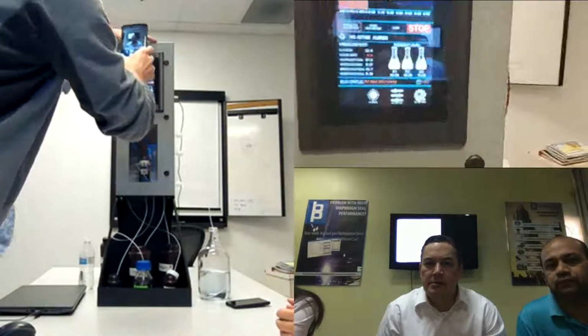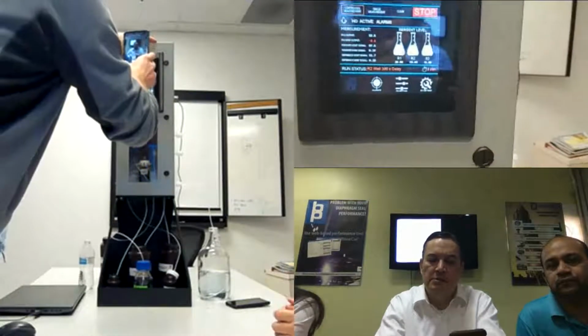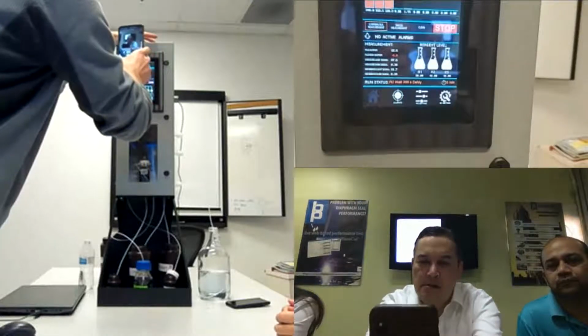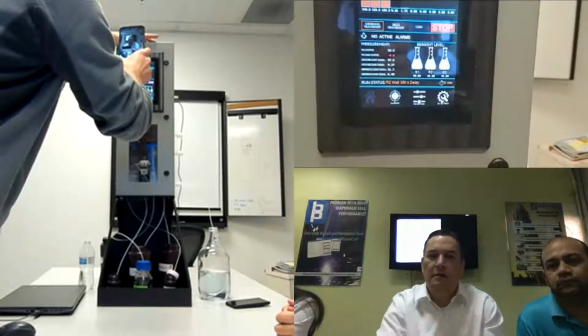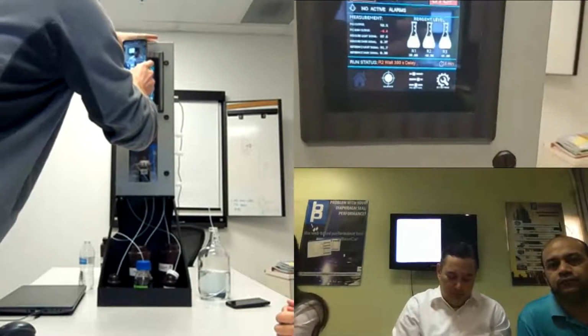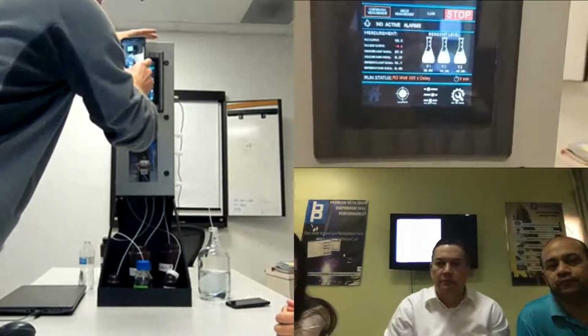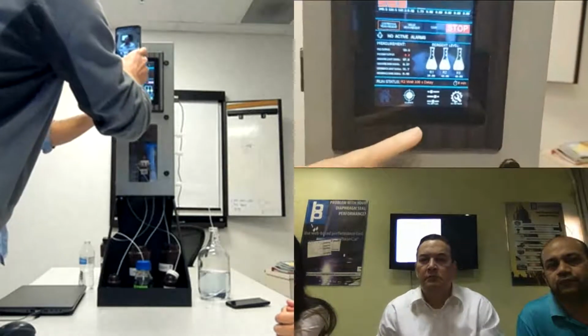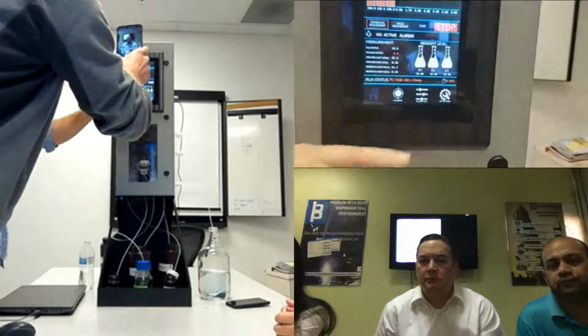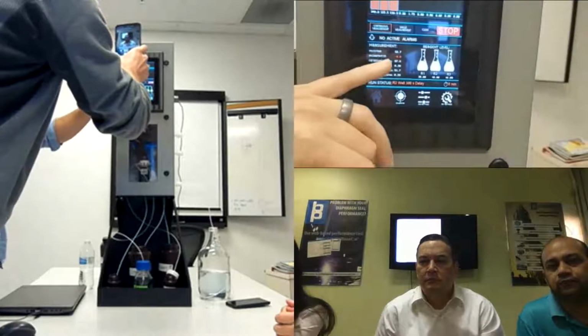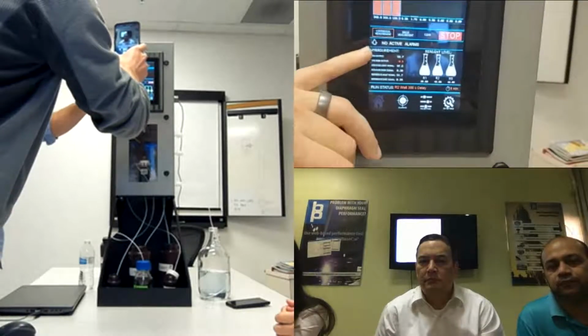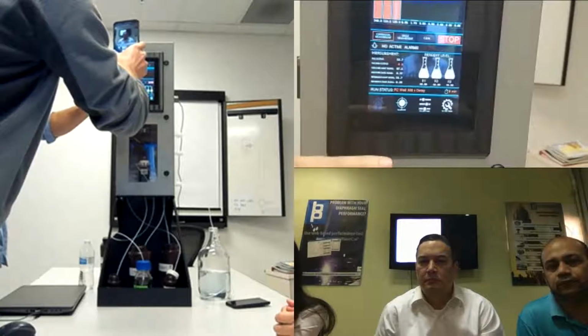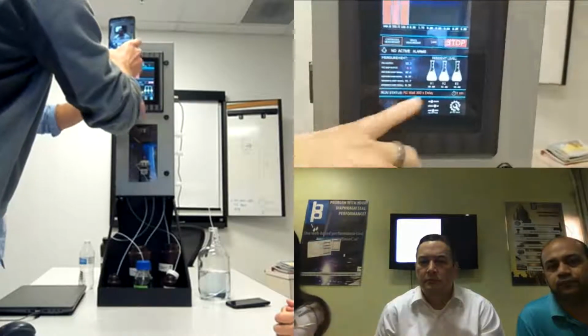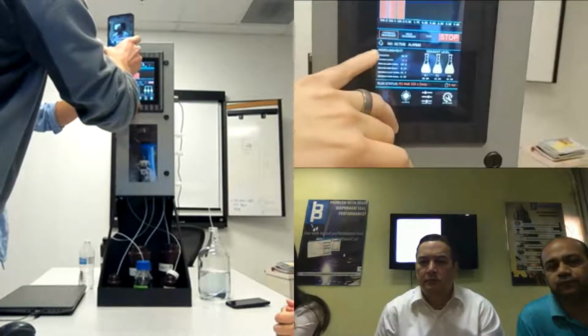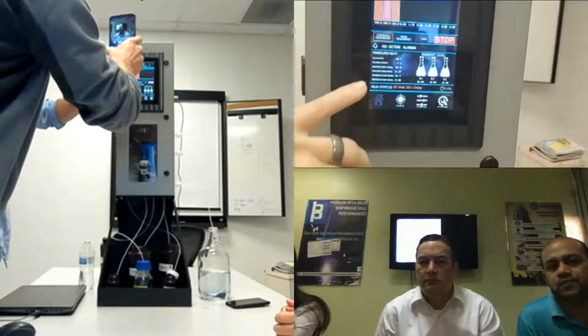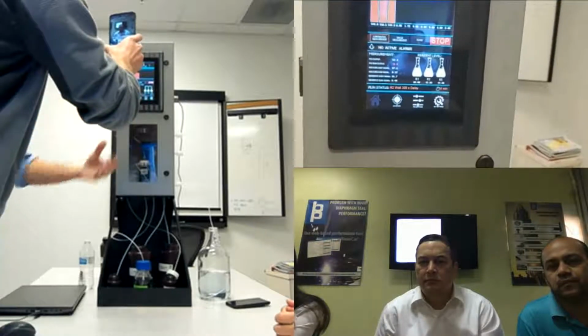Okay, essentially this is the actual home screen of the analyzer. You have a bar chart of your last 10 measurements here. This is really the home base for diagnostic information like reagent levels. If there are any alarms or issues with the instrument, you'll see that on display right here. And it will also give you the option to do continuous measurements, or a single measurement in the event you want to do a grab sample.